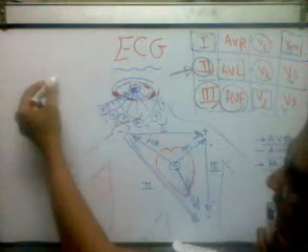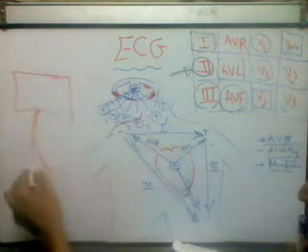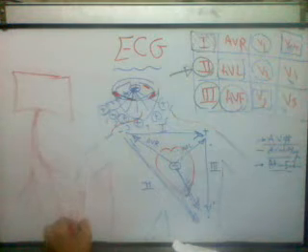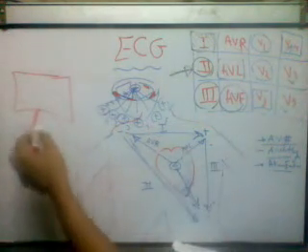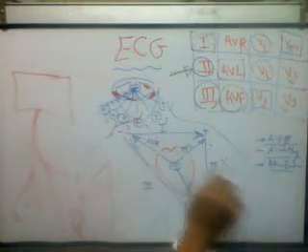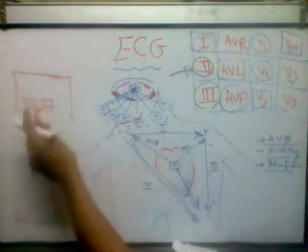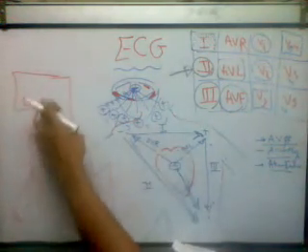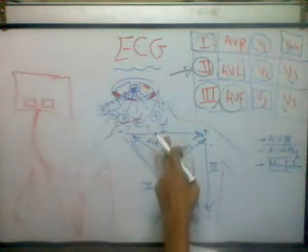The ECG device consists of the control bar and wires. There are two types of wires: limb and chest. Limb wires 1, 2, 3, 4. Every part of this goes to the limbs. And the 6 chest leads go to the chest. And we have a control with automatic or manual. If you use automatic, it will automatically get views of the leads, limb or chest. If you use manual, you can get every lead separately.